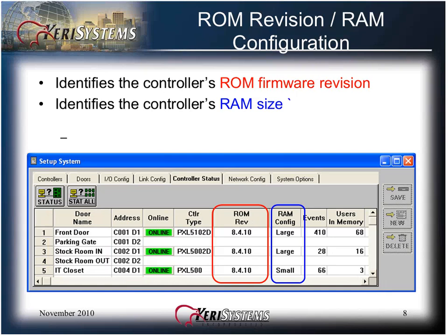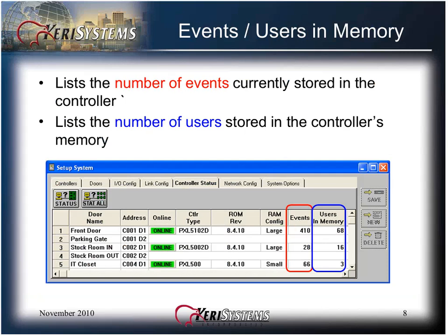The ROM revision column identifies the controller's firmware revision, and the RAM configuration identifies the controller's RAM size. RAM size correlates to the number of users that can be assigned to that controller. The event users in memory columns list the number of events currently stored in the controller. The maximum number of controller events is 3640. The users in memory list how many users are stored in the controller's memory. This number varies depending on the model of the controller.